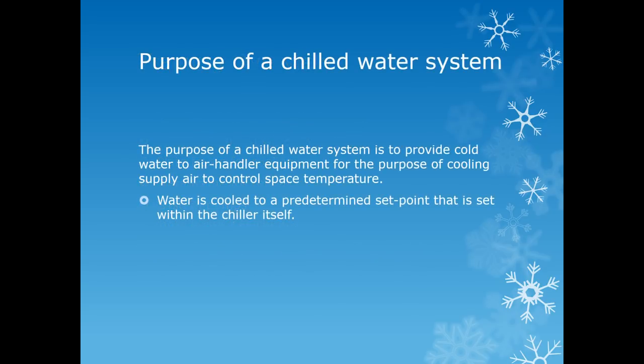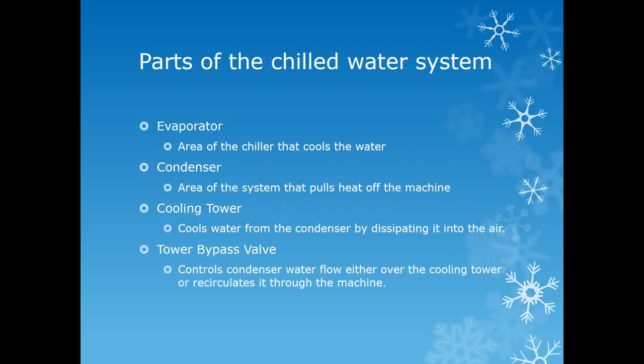The chilled water system is to provide cold water to air handler equipment for the purpose of cooling supply air to control space temperature. Water is cooled to a predetermined set point that is set within the chiller itself. The water system will contain the evaporator side of the chiller, which is the area where the water is cooled.